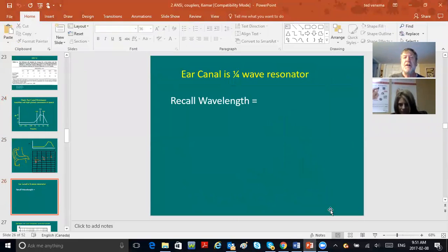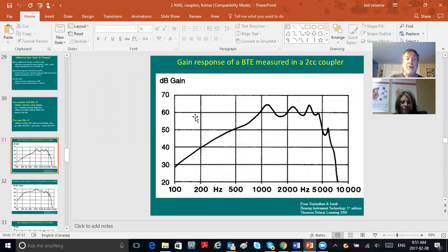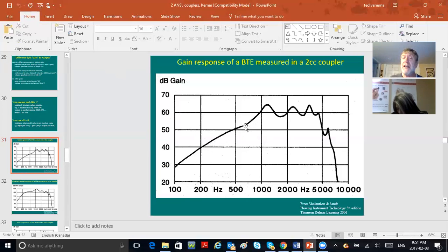Here is a gain response. You can tell it's gain because the vertical axis just says dB, not dB SPL. Also look at the number range—70 to 20—that couldn't be output, because output equals input plus gain, so output would be in the hundreds. Also notice the low frequencies have less gain; when looking at gain responses, usually the most is at mid to high frequencies.